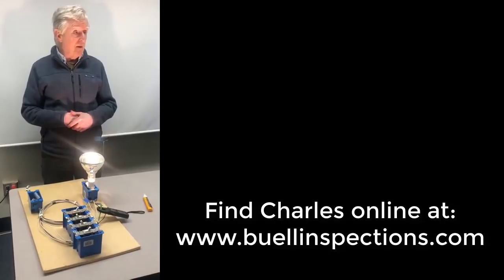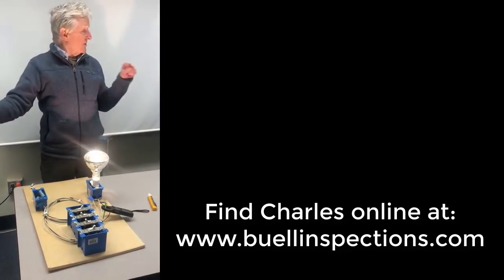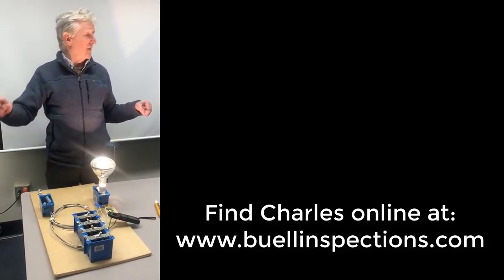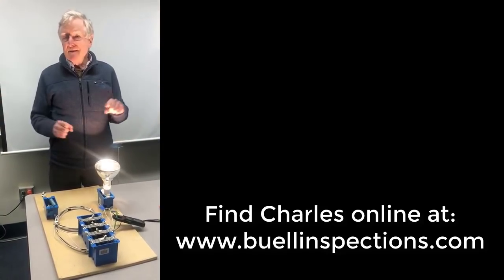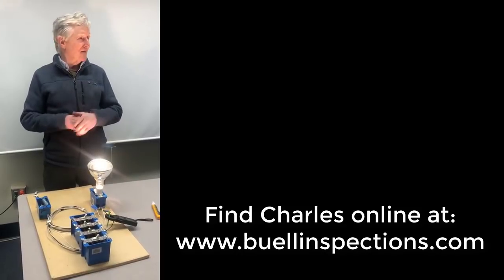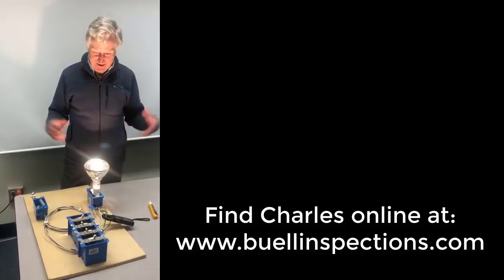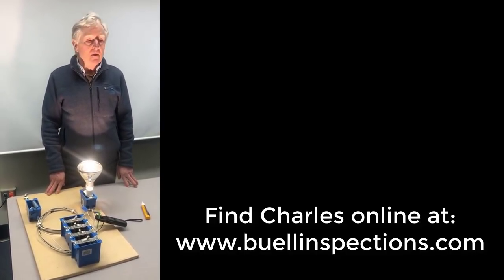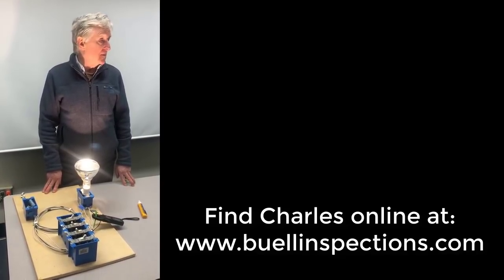So you can clearly see that if I'm in a trench somewhere with the ground wire taken apart, and I hold one end in one hand, the other hand in the other, sayonara in 1.2 microseconds, as they said on Titanic, right? You just can't allow that current to flow through your heart, and that's why we don't connect them together in the subpanel.